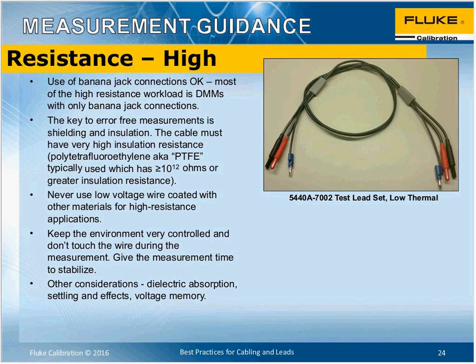The considerations for high resistance measurements are dielectric absorption, settling effects, and voltage memory. We won't go into those in depth today, just because we don't have the time. They are influences that affect this measurement. May I comment there? Yes. We should avoid the use of PVC type insulation leads and those single patch cords here and go over to a good PTFE insulated cable, because it really is what you need for the higher values of resistance.